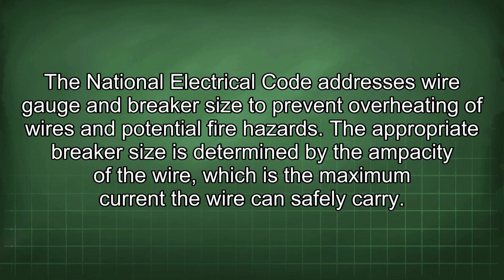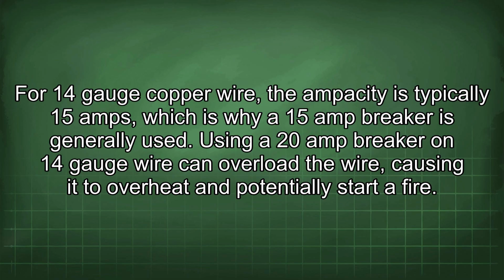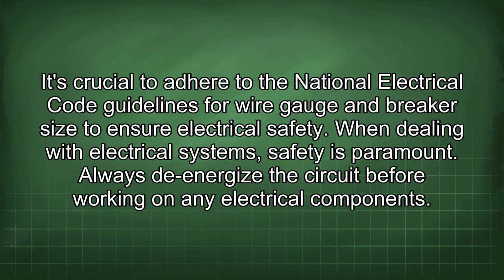The National Electrical Code addresses wire gauge and breaker size to prevent overheating of wires and potential fire hazards. The appropriate breaker size is determined by the ampacity of the wire, which is the maximum current the wire can safely carry. For 14-gauge copper wire, the ampacity is typically 15 amps, which is why a 15-amp breaker is generally used. Using a 20-amp breaker on 14-gauge wire can overload the wire, causing it to overheat and potentially start a fire. It's crucial to adhere to the National Electrical Code guidelines for wire gauge and breaker size to ensure electrical safety. When dealing with electrical systems, safety is paramount.